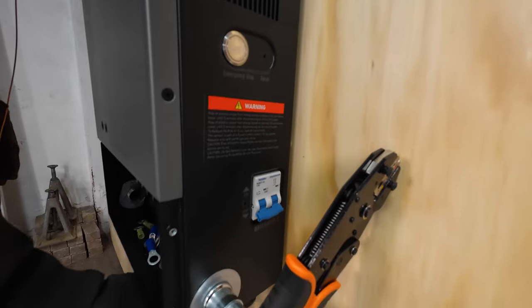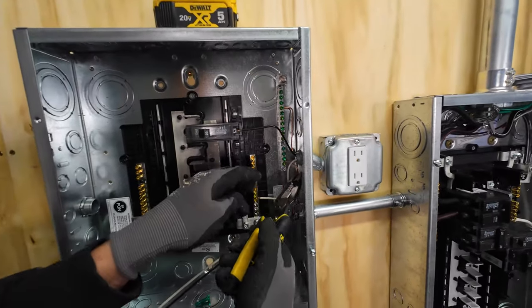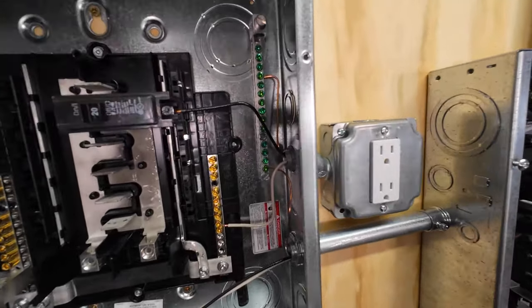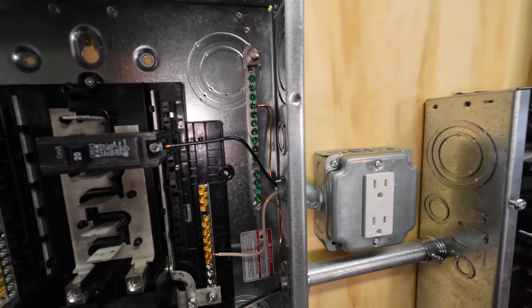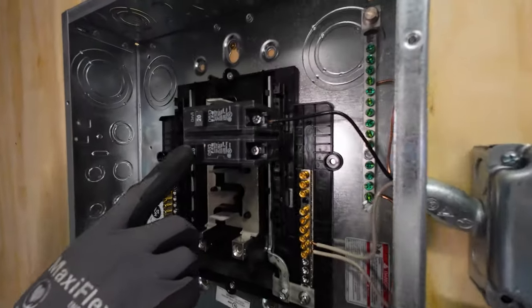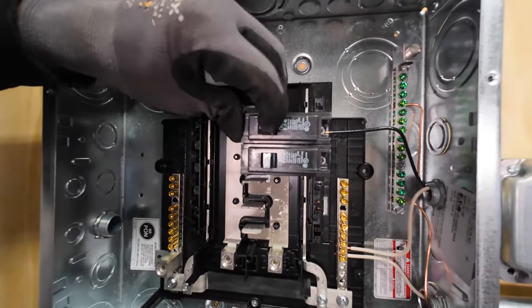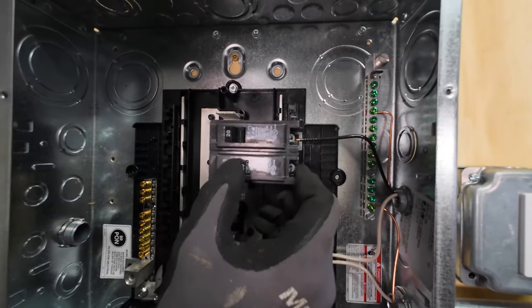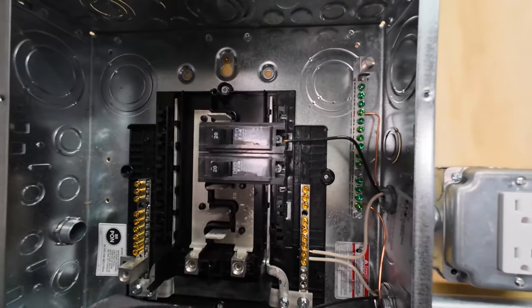As an electrical contractor in Indianapolis, we do save our scrap wire. We produce probably $35,000 a year of scrap steel, aluminum, and copper — makes for a decent Christmas party. The breaker has come to the trip position. What a lot of people don't know is what a breaker's trip position looks like. It's right in the middle — so that's off, that's on, and that's trip. In order to reset a breaker, it has to go fully to the off position and then on.